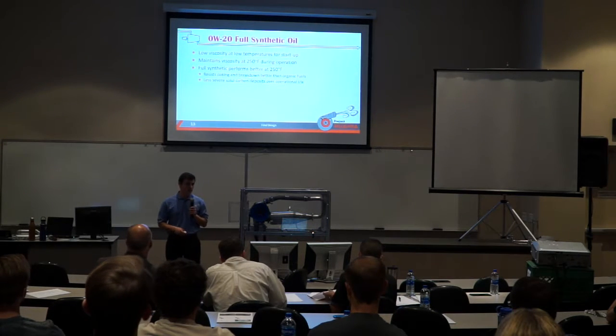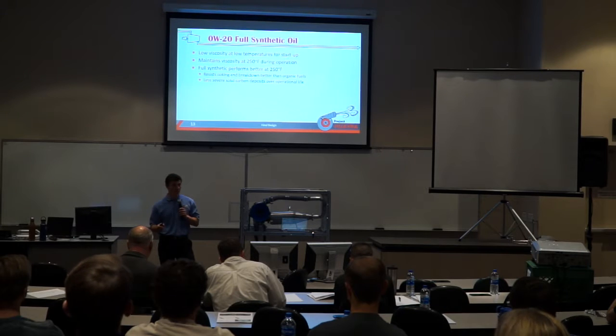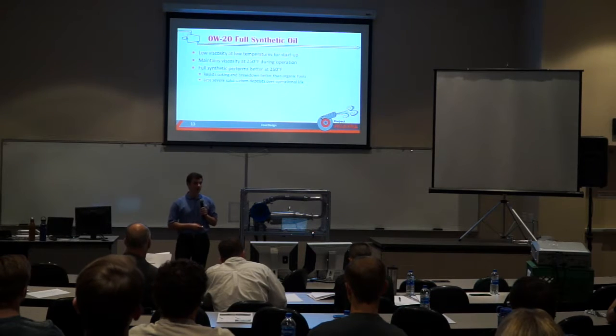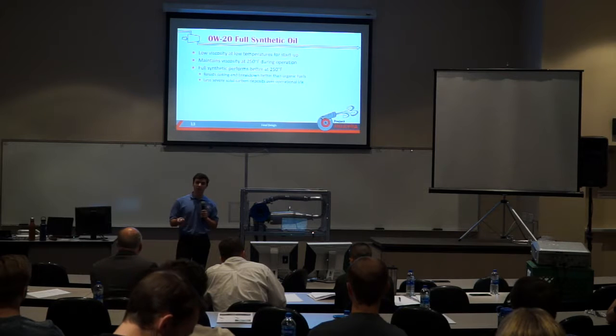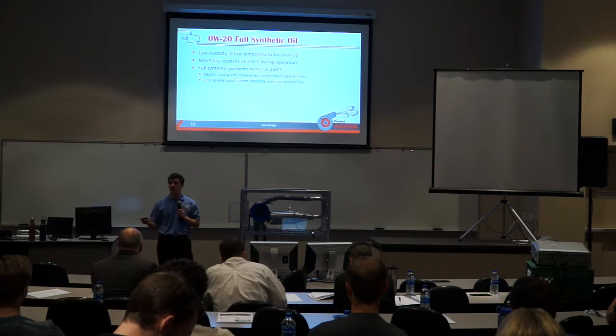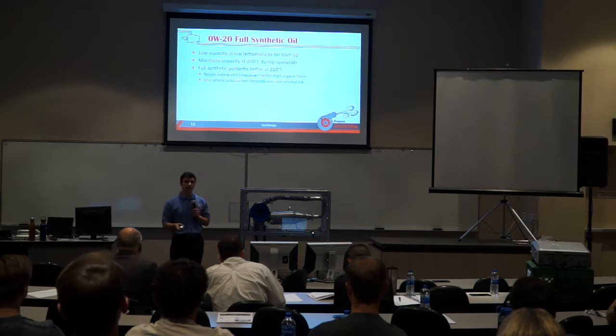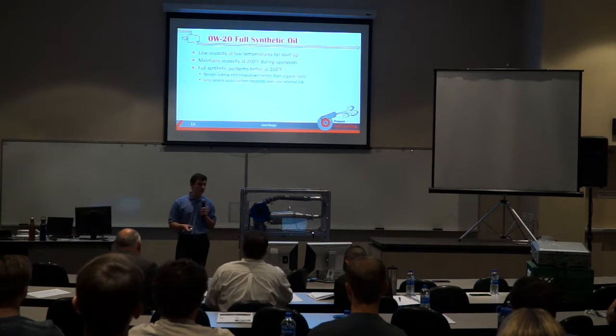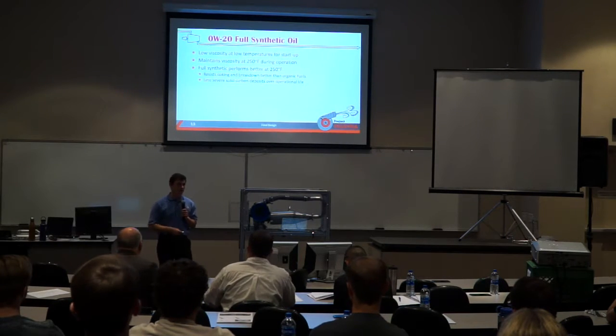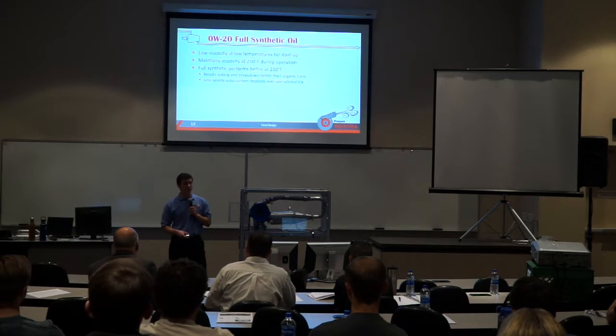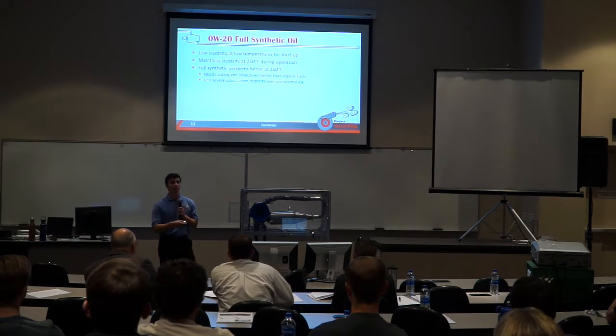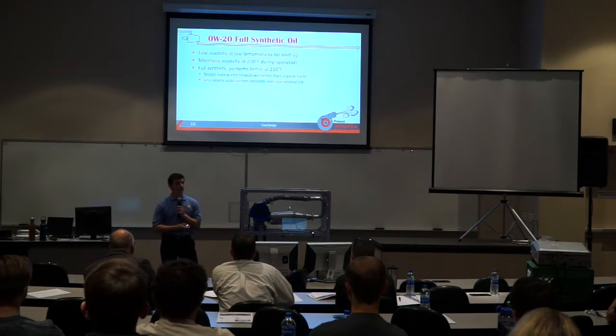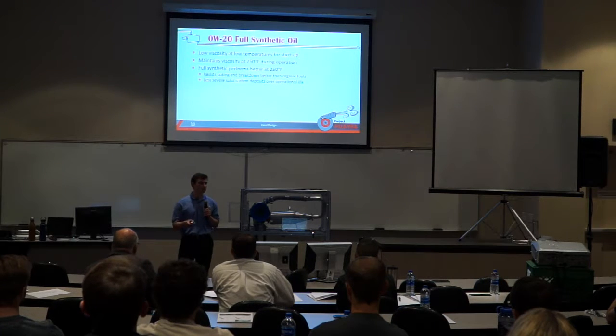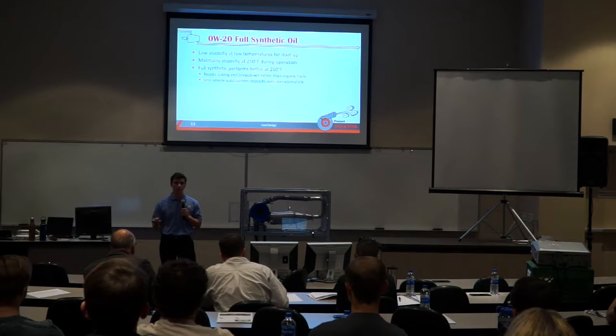For the oil in the system, we decided to use a 0W-20 full synthetic motor oil. We chose this oil because it has low viscosity at lower temperatures for startup, which is where most wear happens in the system. It also maintains its viscosity at our expected operation temperature of 250 degrees Fahrenheit. We chose full synthetic motor oil because it performs better at our expected operation temperature of 250 degrees Fahrenheit by resisting coking or breakdown of the oil better than organic oils. It'll also have less severe solid carbon deposit buildup over the operational life of the engine.